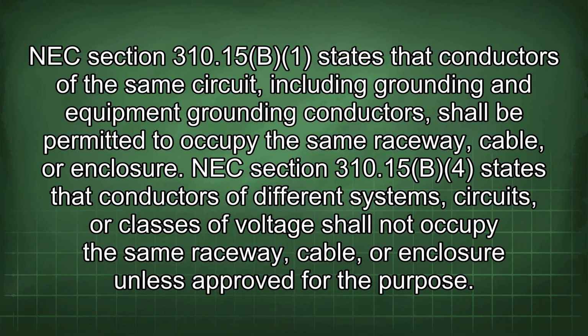NEC Section 310.15 states that conductors of the same circuit, including grounding and equipment grounding conductors, shall be permitted to occupy the same raceway, cable, or enclosure. NEC Section 310.15b states that conductors of different systems, circuits, or classes of voltage shall not occupy the same raceway, cable, or enclosure unless approved for the purpose.